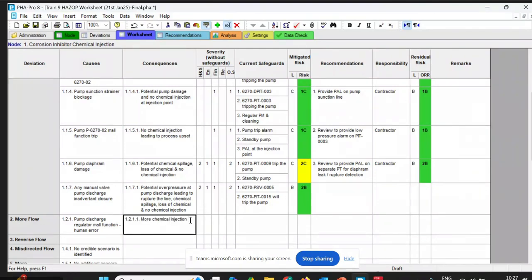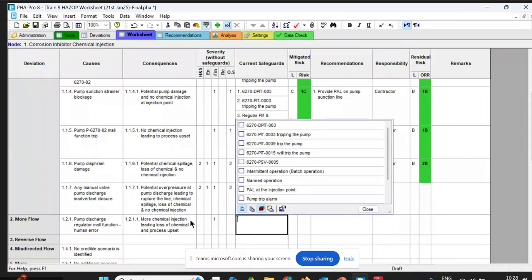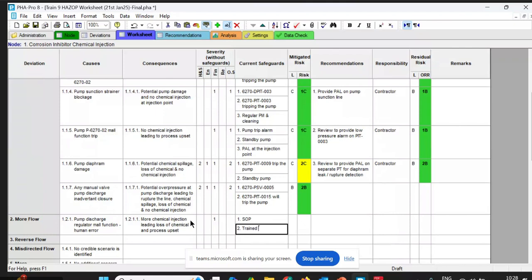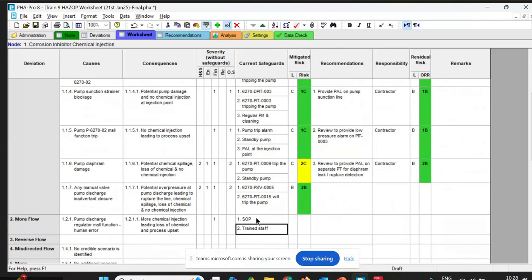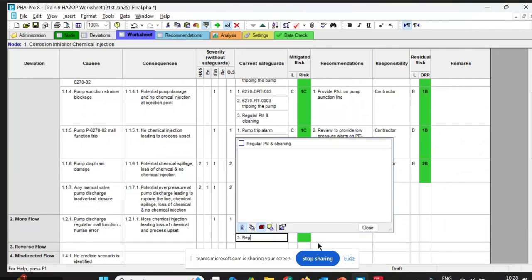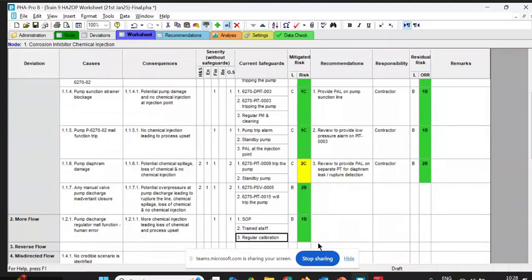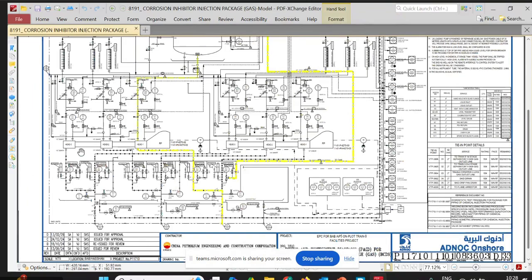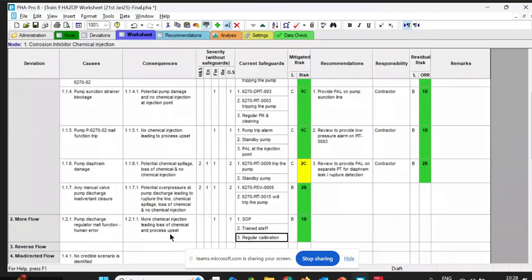Miscalibration or spring failure, and more chemical injection leading to loss of chemical and process upset. Yes, because sometimes more flow is similar to no flow. You are right. So I would say asset 1 and only SOP and trained staff, and pH. Will it increase pH? No. So I think for this case we have only 2 safeguards, SOP and trained staff. And regular calibration, we can say regular calibration. Because you have a calibration port here and you are doing regular calibration, we can take credit. So okay, we are happy.